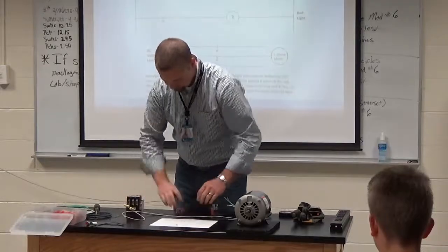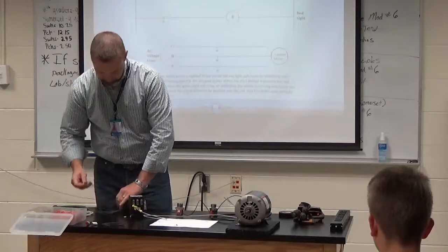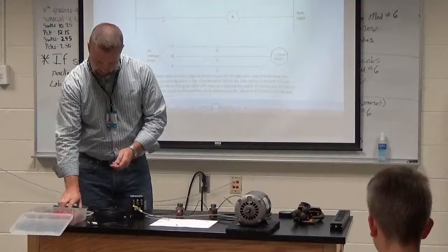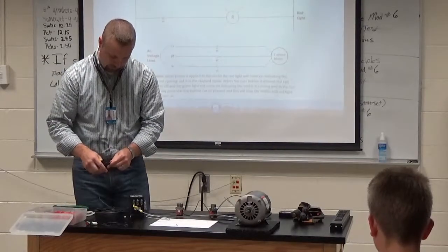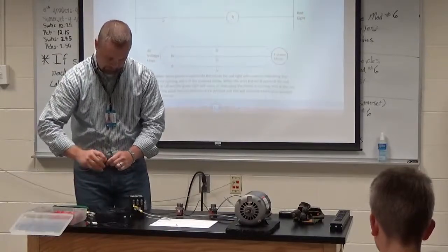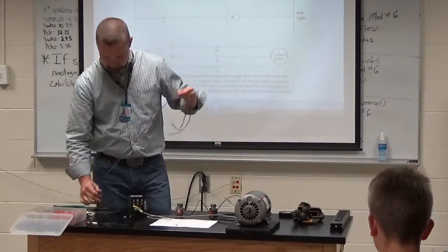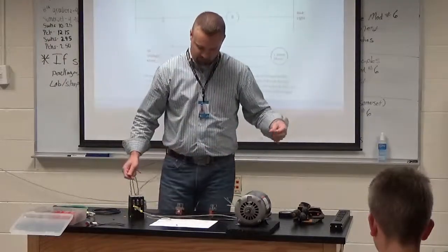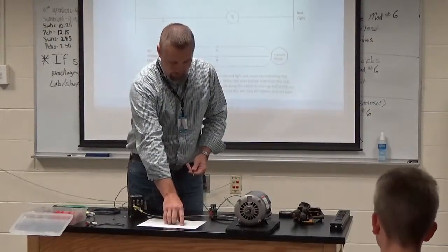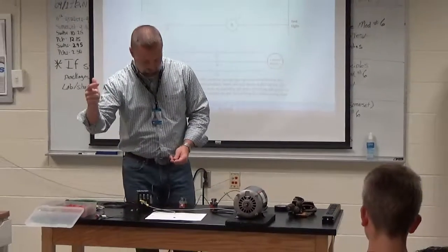Okay, my next step then, guys, is creating my holding circuit, which enables me to take my finger off of that start button and the motor continue running, right? What happens if we don't have that holding circuit, guys? When you let off the button, it'll stop. He's exactly right. Now, on your schematics, you see the holding circuit ties back in where? Right before the start button. Yes, before the start button, Travis.